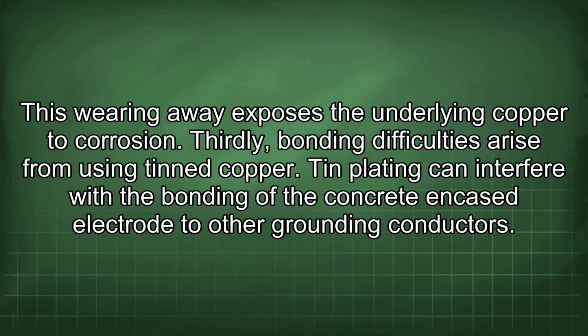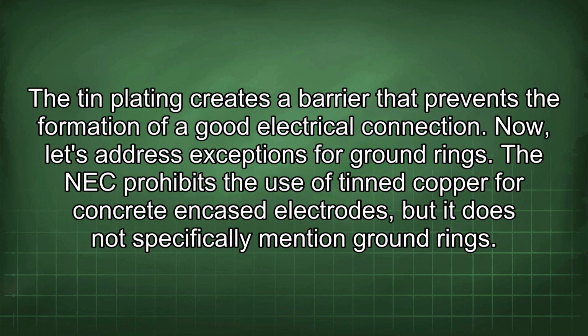Thirdly, bonding difficulties arise from using tinned copper. Tin plating can interfere with the bonding of the concrete encased electrode to other grounding conductors. The tin plating creates a barrier that prevents the formation of a good electrical connection.